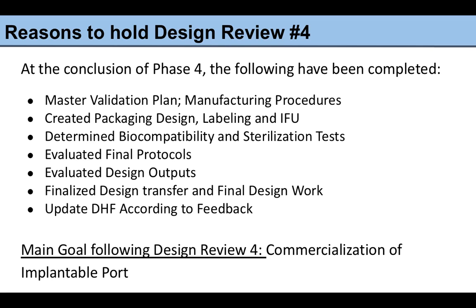The team is holding this design review number 4, because at the end of this phase, we have completed a master validation plan and manufacturing procedures. We've created a packaging design, labeling, and IFU. We've determined biocompatibility and sterilization tests. We've evaluated our final protocols. We've evaluated design outputs. We've finalized our design transfer and final design work, and we've also updated our DHF. The main goal of this design review is to work towards the commercialization of our implantable port.